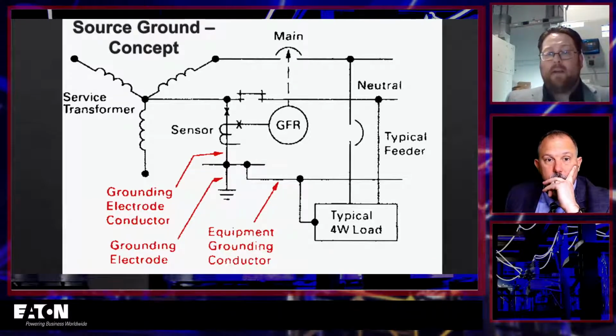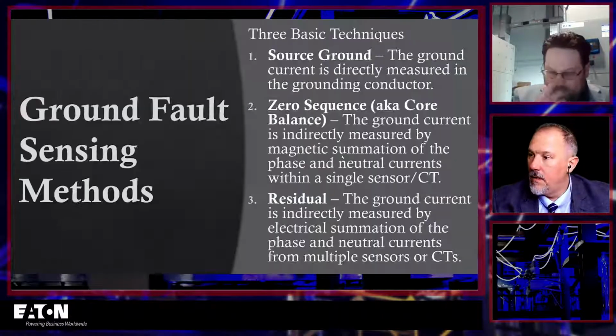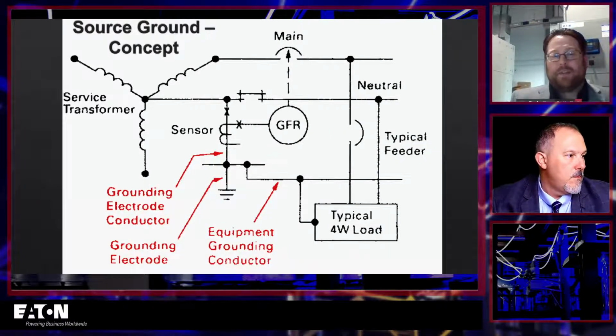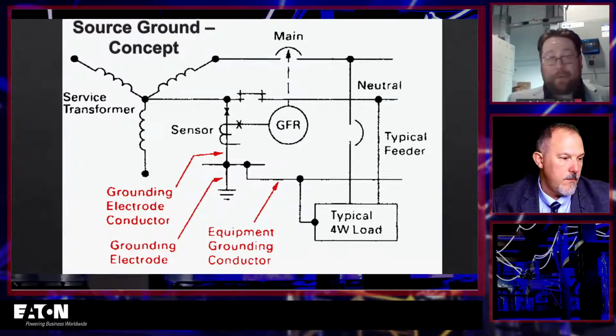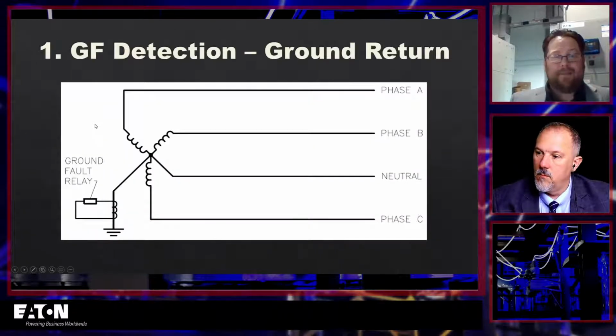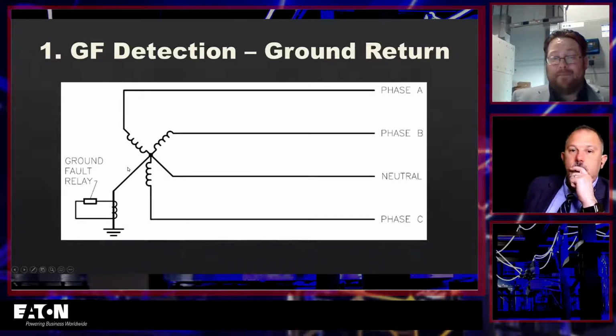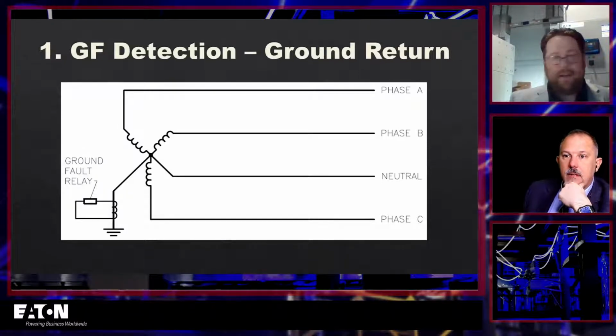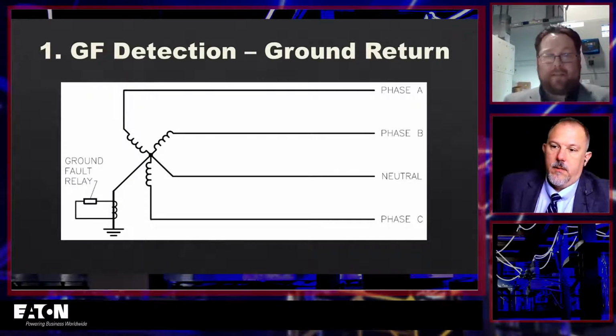Yep, and we're making sure that there's no current flow there ultimately. That's what we're looking for, that current flow. What you're missing in this diagram is, if you imagine where that box is that says 4-wire load, and you had a fault there and drew a little ground symbol, that phase current from phase A, B, or C would flow down into ground, and then come back up through that grounding conductor, through that CT, that sensor, and go back to the neutral point on the source itself, which could be a generator or a transformer. That's the unusual path we're looking for.